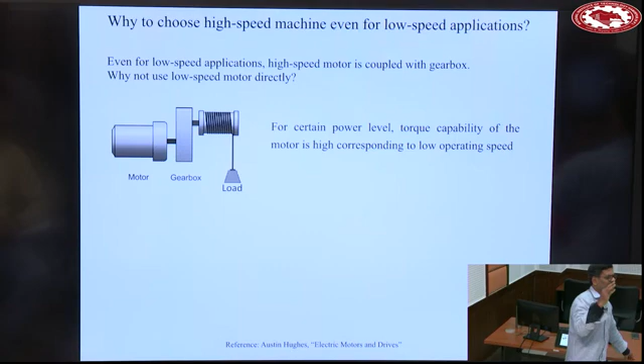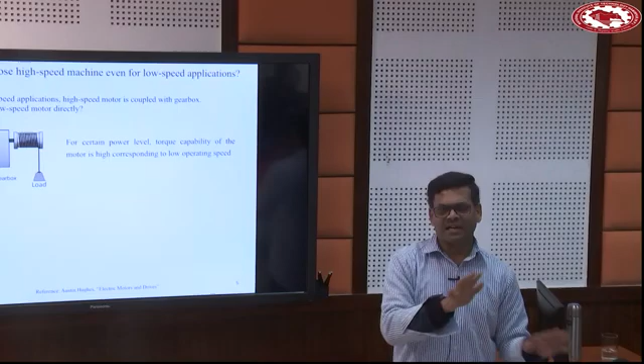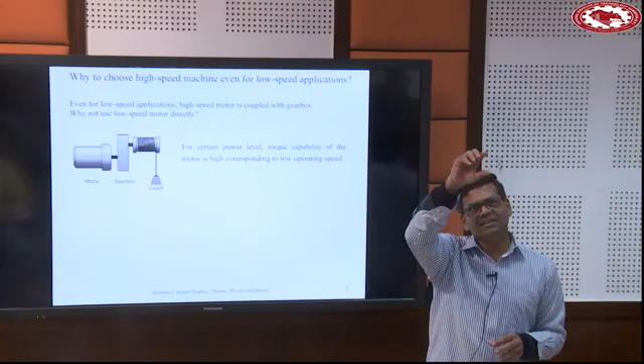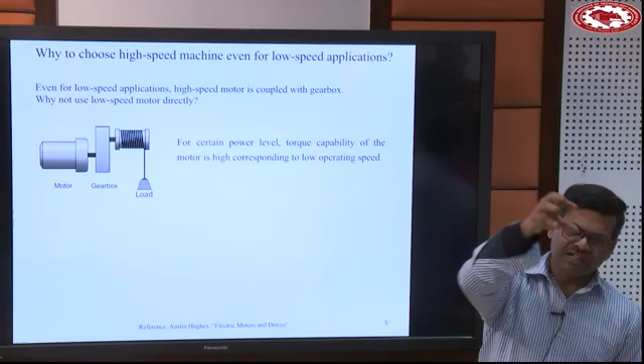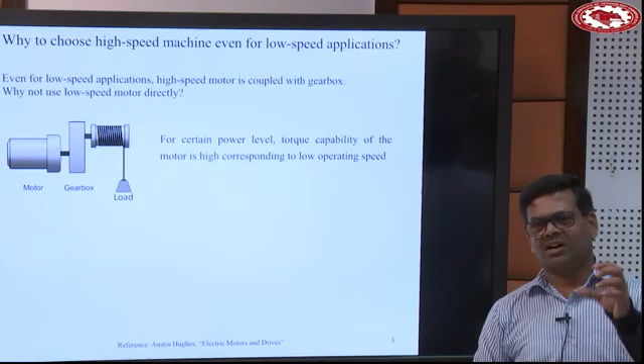Therefore torque is proportional to flux density and current. So now if you want high torque, then current has to be high, right? 100 RPM motor, 1500 RPM motor. Obviously with the 100 RPM motor, the current has to be more. If the current has to be more, you have the slots and teeth. I am talking about the stator. So then you have to inject more current in the conductors which are sitting in the slot. So if you have to inject more current, then the cross sectional area of the conductor has to be high.